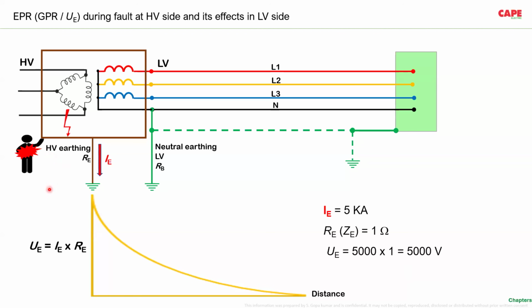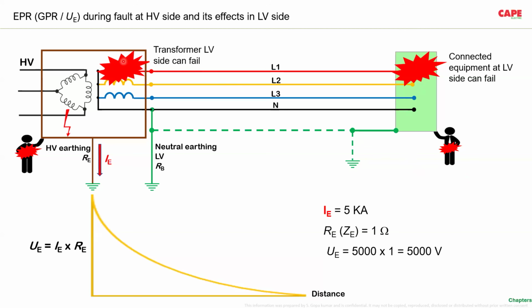A person who is touching a metallic object in the high voltage installation will, of course, get a shock because 5000 volt is much higher than the tolerable limit of touch voltage. The person touching any metallic objects in the substation will get a shock. A person who is touching the low voltage equipment connected to the same transformer also may get a shock if you don't take care of that particular potential. Connected equipment also will fail if you don't take care. The low voltage side of the transformer also may fail.